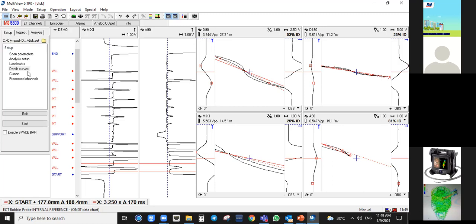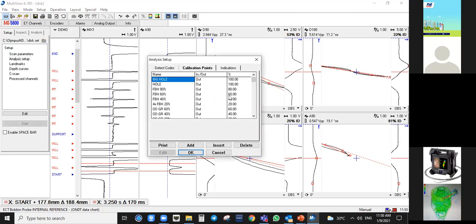Okay. So you mean to say that the specific groove is not like 40, not 20. You can still do that. When you are doing the system calibration, under analysis setup, calibration points, you can just choose the percentage here. For example, if you have an OD groove that is, instead of 60, you put 80.